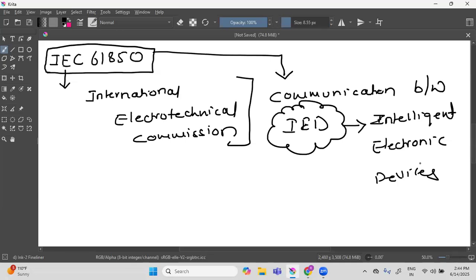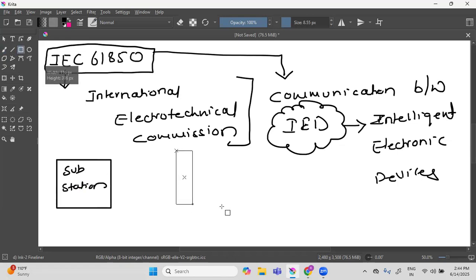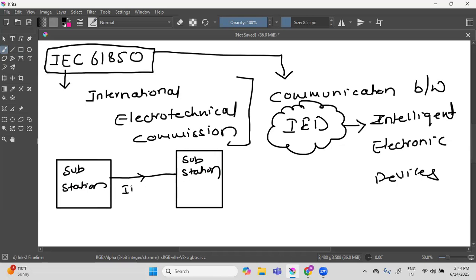Now, from substation to substation, there will be one IED in one substation. For example, I have a substation - you know what a substation is, the power transmission center. I have one substation, and I have another substation like this. When power is transmitting from here to here, the communication between these two transmissions will be taken by IEC 61850. Why? Because in this substation there will be one device - the pink color box I'm using here. These devices I'm calling IEDs, intelligent electronic devices.